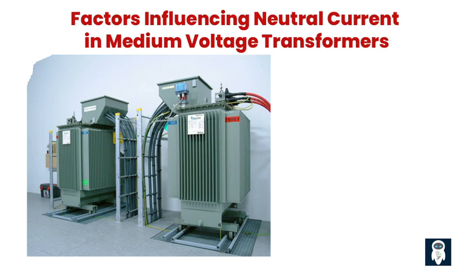2. Harmonic distortion and its impact on neutral current. Harmonic distortion refers to the presence of unwanted frequencies in the electrical system. Non-linear loads such as computers, variable speed drives, and lighting systems can introduce harmonic currents. These harmonic currents can cause increased neutral current and voltage distortion, impacting the performance of the transformer.